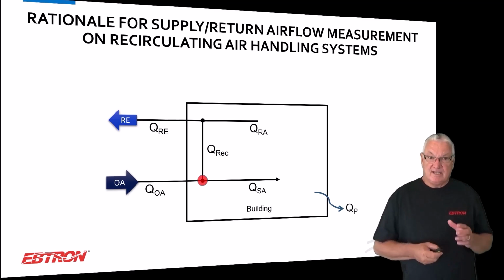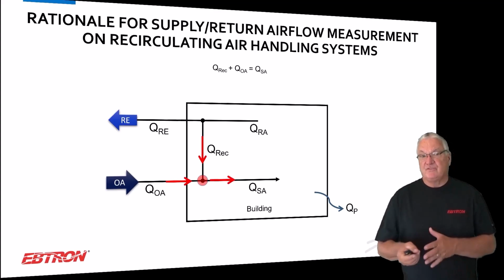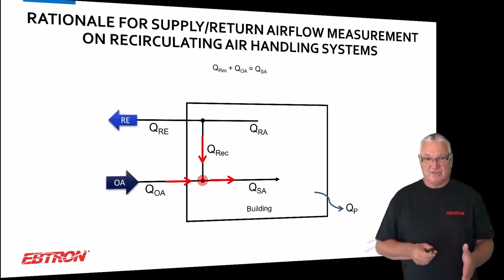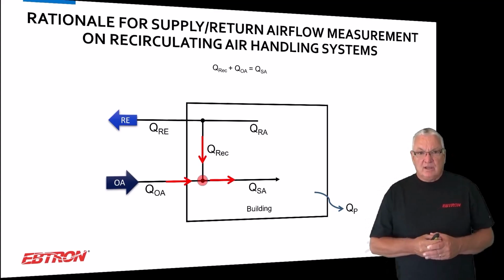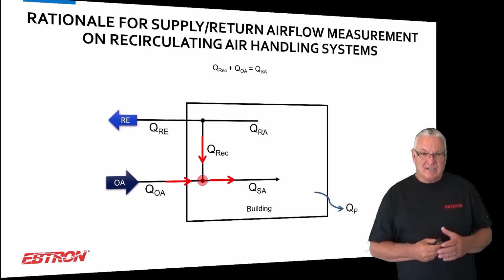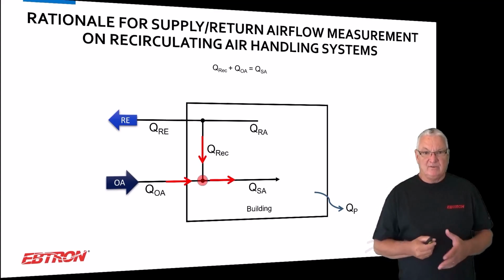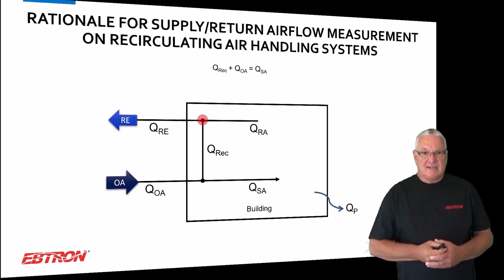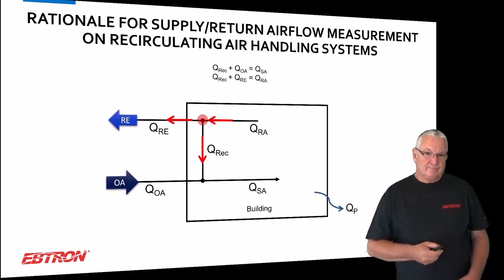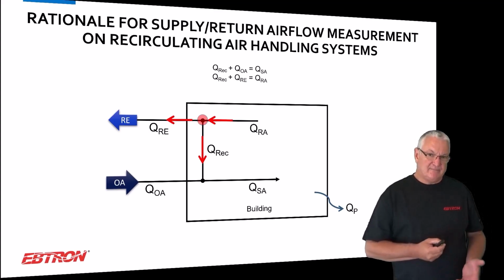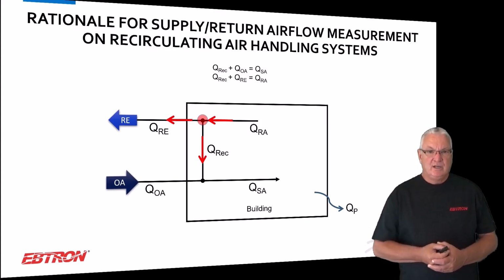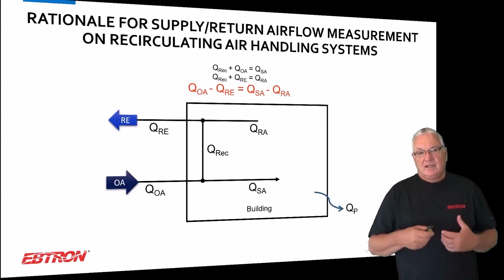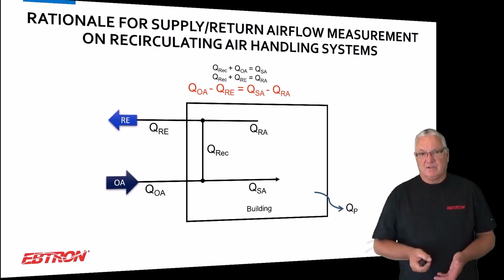What I like to do is say, look, let's make this really kind of simple. If I look at this point here, I can make an equation. For those of you that are not understanding why I'm saying measure supply and return, I can make an equation that says that the recirculated airflow rate plus the outside airflow rate equals the supply airflow rate, and that's an equation I put up there in the middle. I can look at this point here, and I can say, hey, the relief airflow rate plus the recirculated airflow rate is the return airflow rate. So there's another equation. I have two equations. I subtract them. Outside air minus relief airflow rates equals supply air minus return airflow rate.